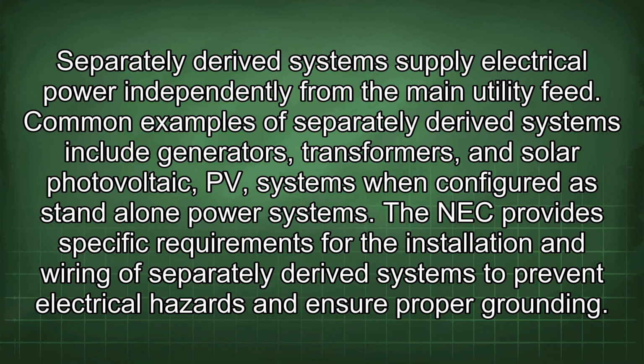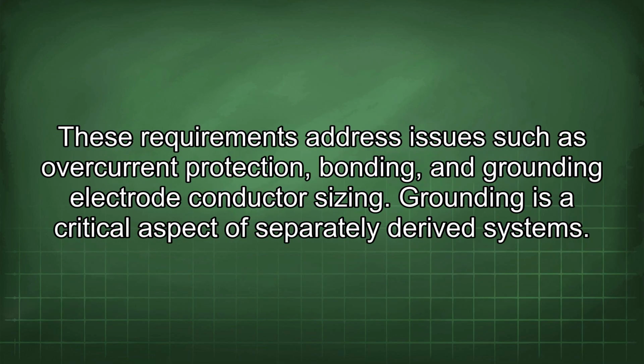Common examples of separately derived systems include generators, transformers, and solar photovoltaic (PV) systems when configured as standalone power systems. The NEC provides specific requirements for the installation and wiring of separately derived systems to prevent electrical hazards and ensure proper grounding. These requirements address issues such as overcurrent protection, bonding, and grounding electrode conductor sizing.